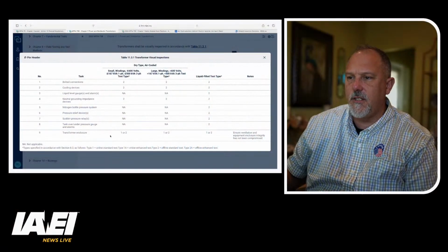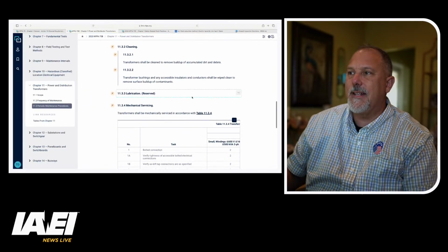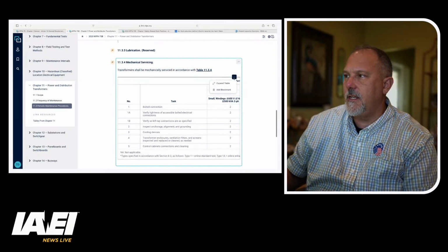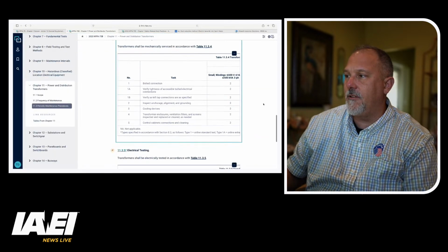I could see a debate going on if I look, and let's take a look at a transformer. Let's take a look at 70B. Transformers are covered in chapter... where's a transformer covered? Hold on. We've got 11, power distribution transformers. All right, so transformers, frequency of maintenance. So visual inspections: there's nothing in the visual inspections that is required to be performed while energized. Cleaning, lubrication, mechanical servicing, I would highly doubt there's anything here that is required to be done energized.